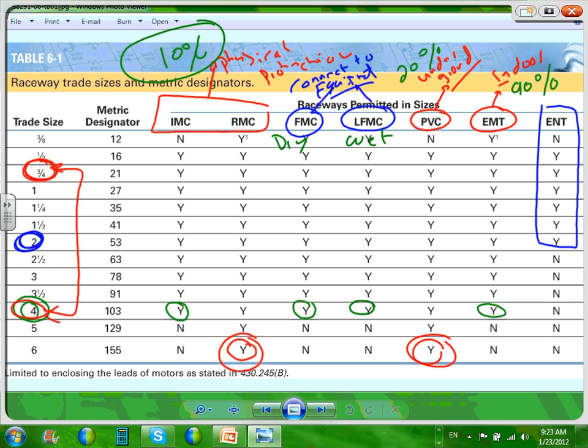Where would you use this conduit? Where would you use this conduit? Hospitals? Well, for a hospital, you can use EMT conduit. Where would you use it where you cannot use EMT? That's my question, because EMT you can use in hospitals, also MC cable. Where would you use the ENT where you cannot use any other conduits?